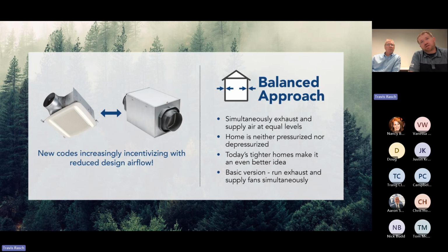And finally, there's another approach, which is the balance approach. And so this is taking those 2 products and making them work together. So if we have an exhaust fan set at 55 CFM and we've got our supply fan set at 55 CFM, we're basically neutralizing that pressure within the building, taking a balanced approach. Again, this is not having any recovery related to this approach. This is something that's used in those much more mild climate zones. Think San Diego, California, or areas in the country where the outside air and the inside air typically aren't that much different.